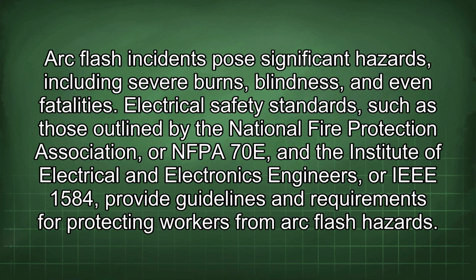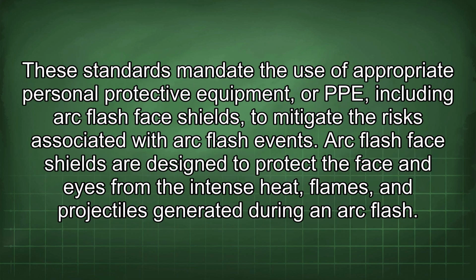Arc flash incidents pose significant hazards, including severe burns, blindness, and even fatalities. Electrical safety standards, such as those outlined by the National Fire Protection Association (NFPA 70E) and the Institute of Electrical and Electronics Engineers (IEEE 1584), provide guidelines and requirements for protecting workers from arc flash hazards. These standards mandate the use of appropriate personal protective equipment (PPE), including arc flash face shields, to mitigate the risks associated with arc flash events.